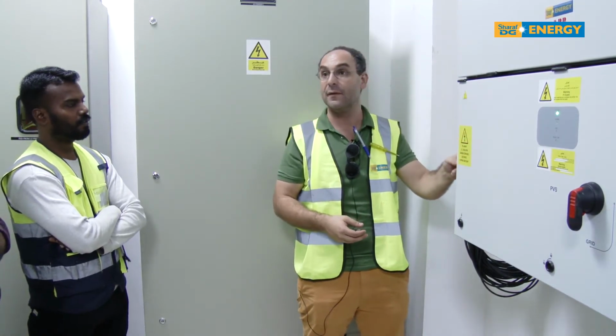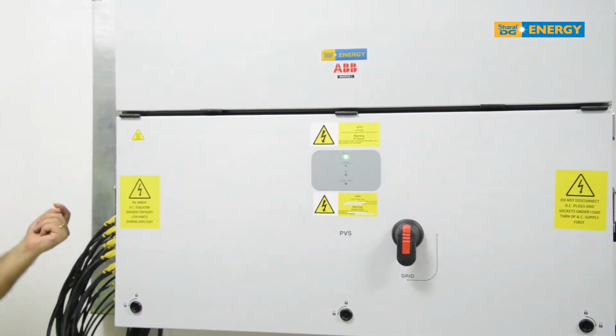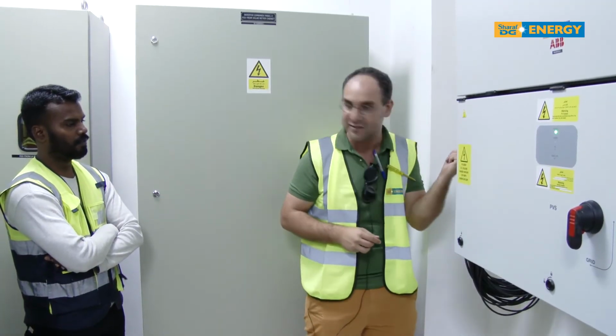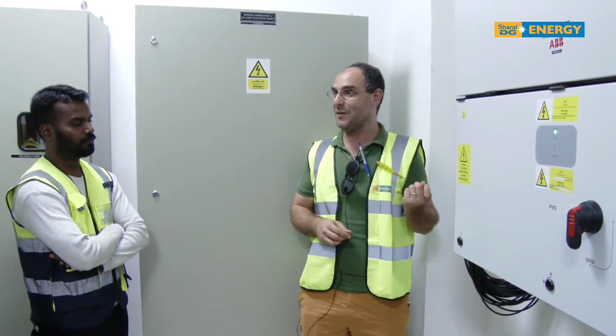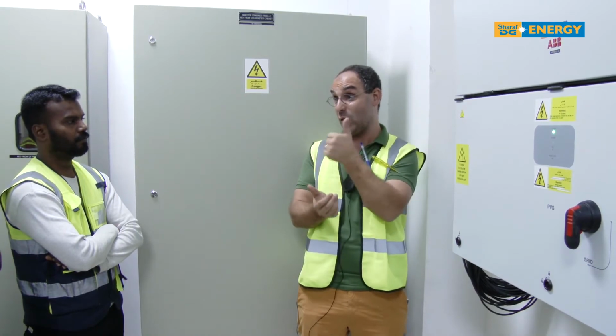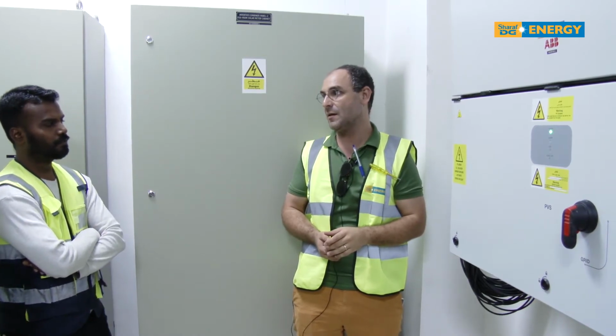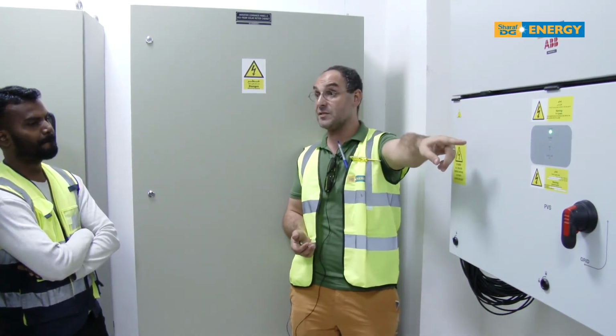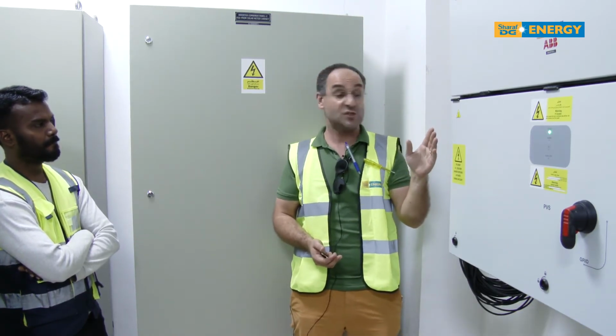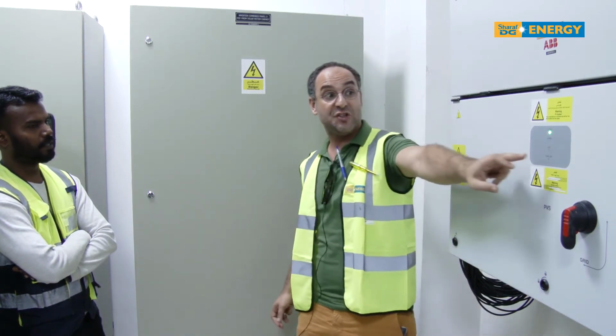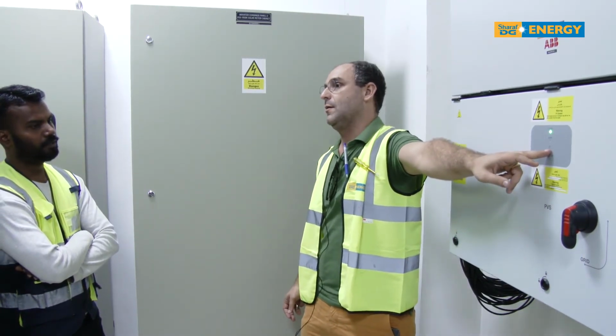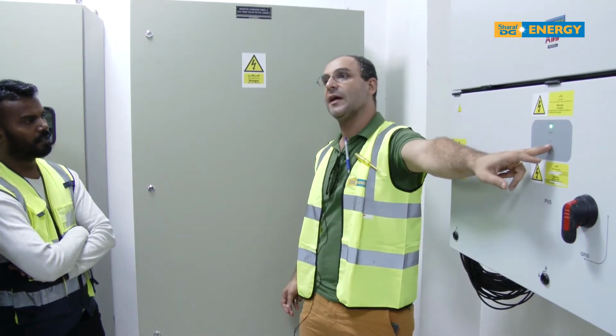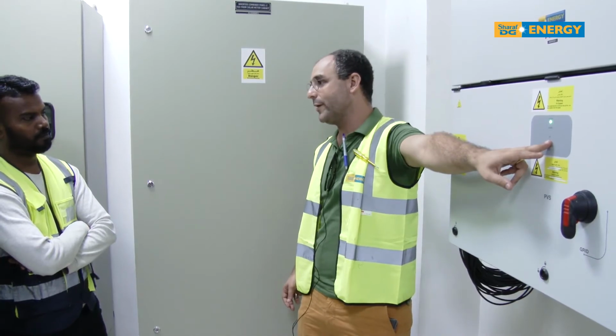The inverter sends up to 1000 volts of pressure and sees whatever comes out on the other side. If it comes in the same range, it means you don't have a cut in the cable. Know what I mean? And therefore the insulation is okay, so people can touch here and nothing happens. Are you with me? Clear? But if that alarm comes, it means we have a passage somewhere. So then, this is a fault: just register the fault and call us, call someone to help us out.